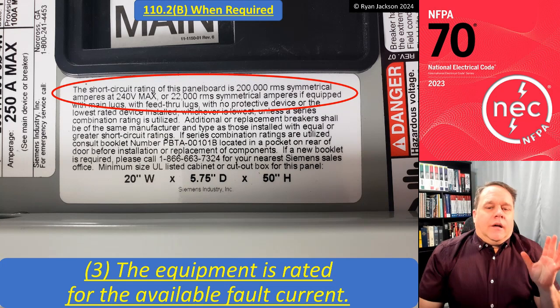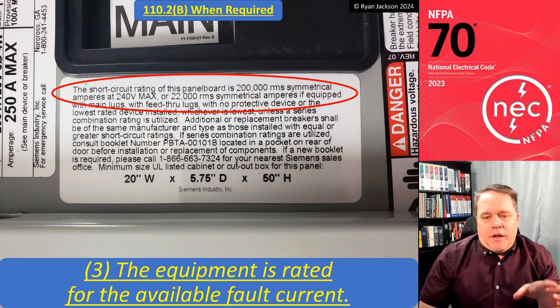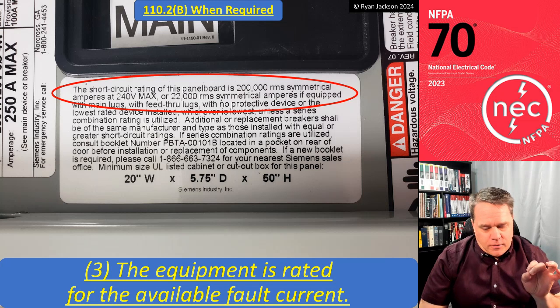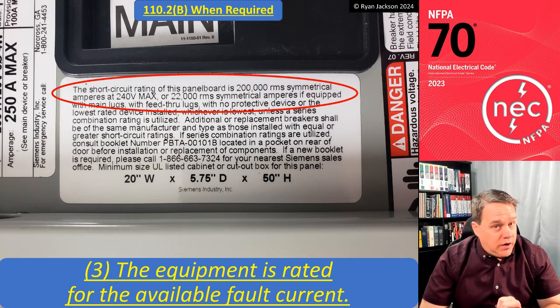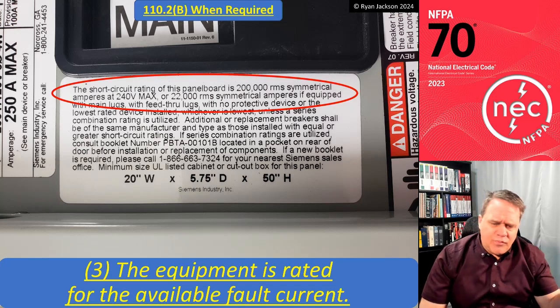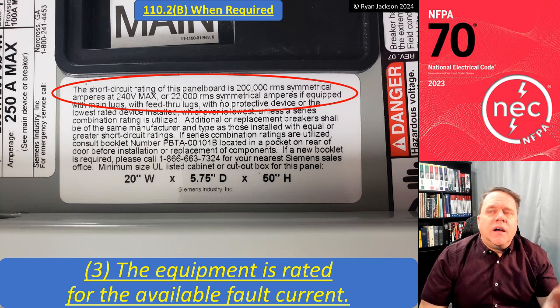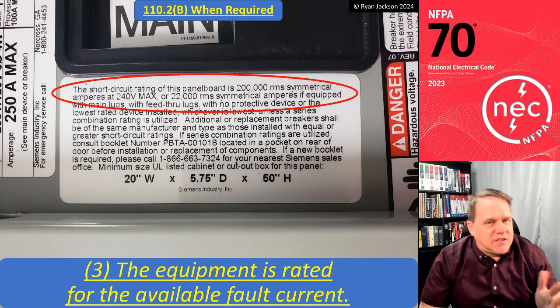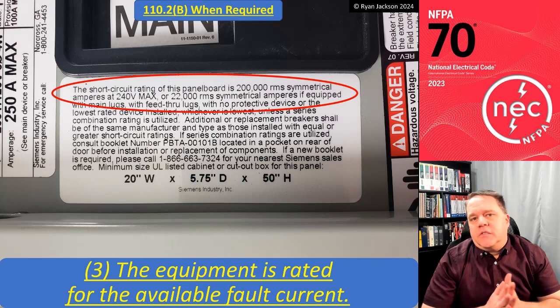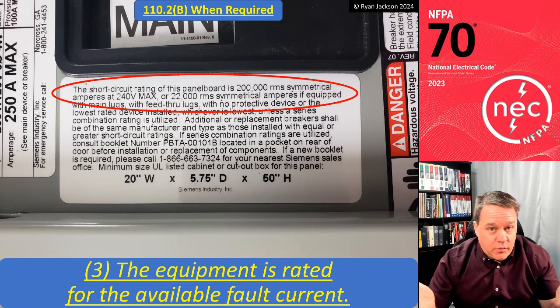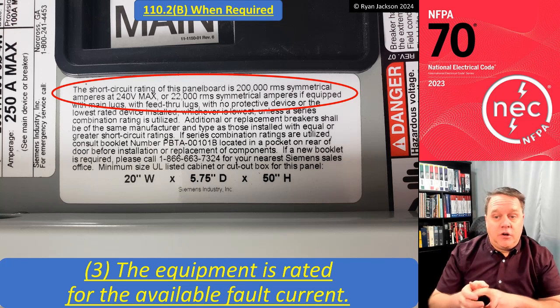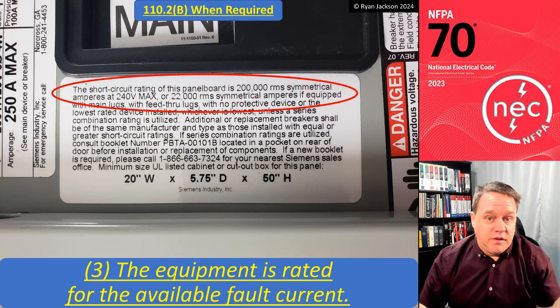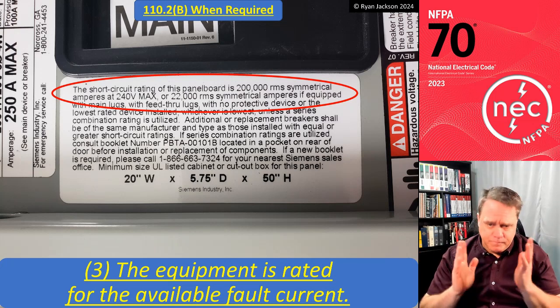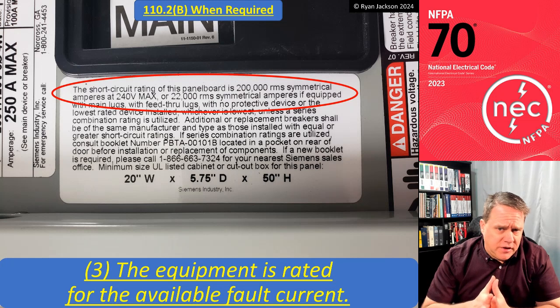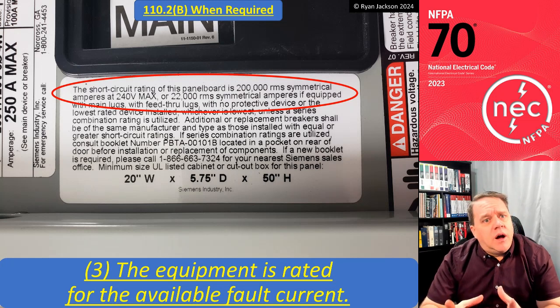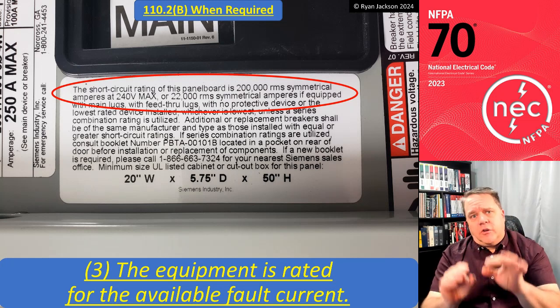Item 3. The equipment needs to be rated for the available fault current. Now, that's added here in the 2024 code. Is it new? Not necessarily. I mean, one of the things that the standard has always said is that the equipment has to be properly installed and installed in accordance with the instructions, which would include that it's rated for the available fault current. But this is an important enough concept that we want to add it here so that it stands alone.